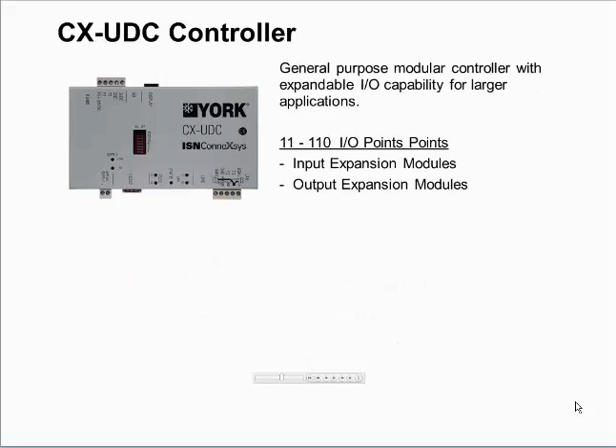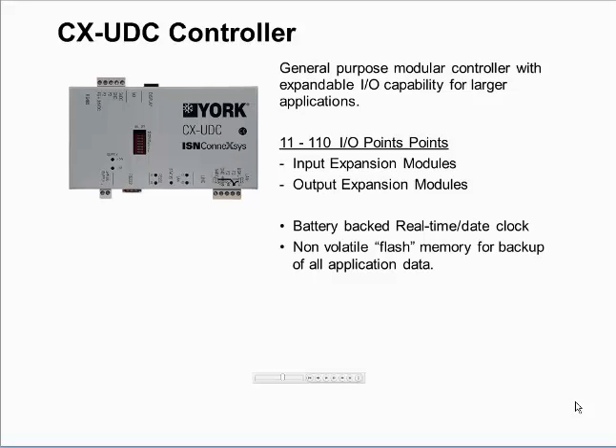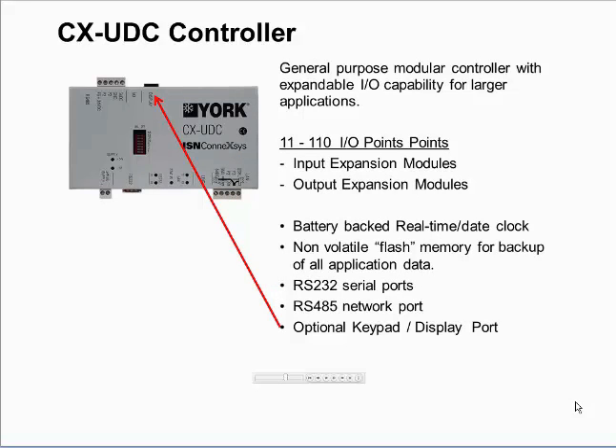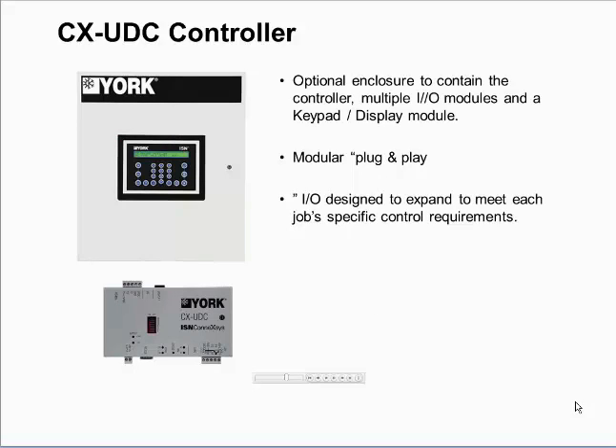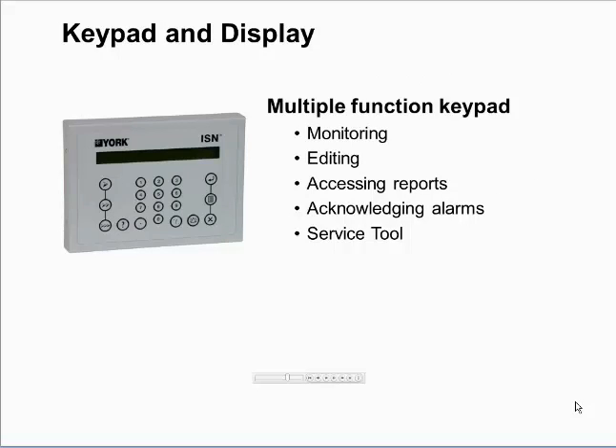The UDC is a general-purpose modular controller designed for larger applications. It has an I/O capability of 11 to 110 I/O points using input and output expansion modules. There is a battery-backed real-time date clock, and a non-volatile flash memory for backup of all application data. An RS-232 serial port for connection of a PC or terminal for programming and monitoring. The RS-485 network port is used to connect to other ISN controllers. And an optional keypad display port. The UDC optional enclosure is designed to contain the controller, multiple I/O modules and the keypad display module. The keypad display module is designed for monitoring and editing, accessing reports, acknowledging alarms, and also as a service tool.